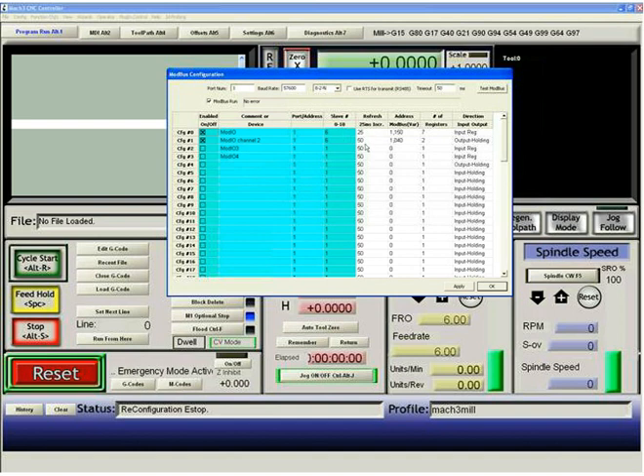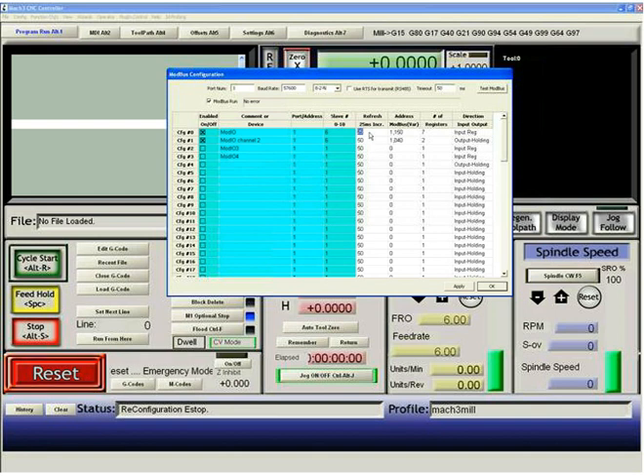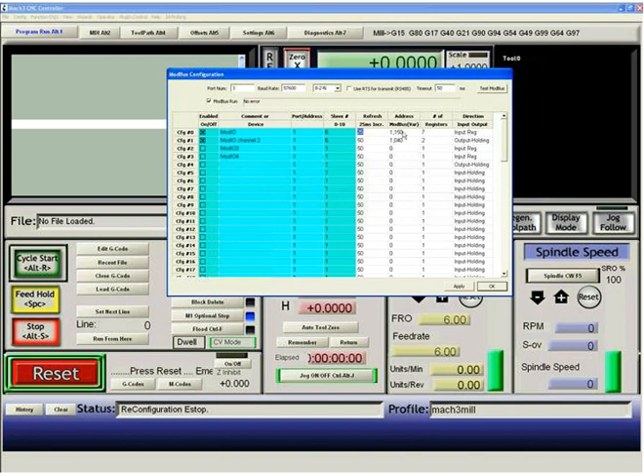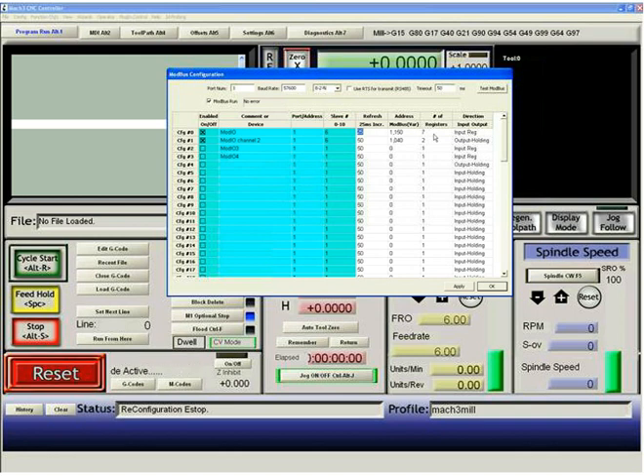And we can also tell it how often to refresh the data. So on 25 milliseconds, this tells the serial system to refresh this configuration 0 every 25 milliseconds. We are telling it the Modbus variables are located at 1150, and we want 7 of them.